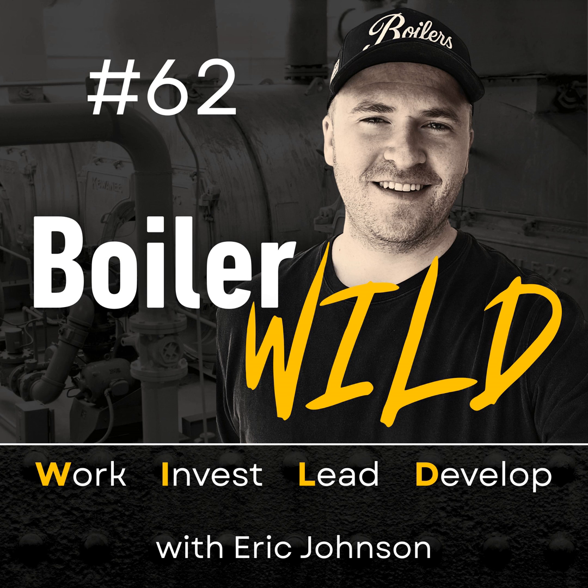Don't pick up the tools right away. You need to observe. Walk around the boiler, observe, slow down. All right. What is the boiler doing? So then you're going to go into the alarm history. And a lot of people will say, oh, well, we left it locked out, because they don't realize there's an alarm history. If you have a 7800, it saves the last 5 or so. It depends on the age of the 7800, but it saves the last 5 or so alarms.